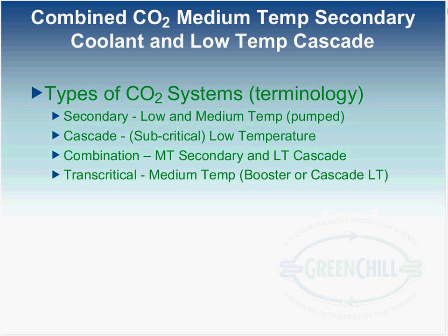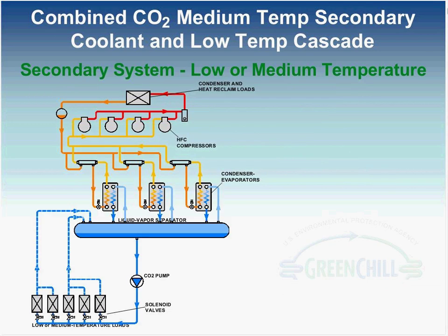Okay, excuse me. Another clarification there is that with GreenChill Partners there are several more, maybe getting close to 20 of those type systems installed, the cascade systems. So a little bit of a clarification there and terminology explanation. I first spoke about secondary CO2 systems, and then Dustin just described the cascade, or what's also called subcritical systems, which are typically used as low temp. I'm going to talk about a combination system that combines medium temp secondary and low temp cascade. And then Travis is going to speak about medium temp transcritical systems, where you can add a low temp booster or cascade to that transcritical as well. So the terminology can be quite confusing, and there are a lot of new terms, especially for North America.